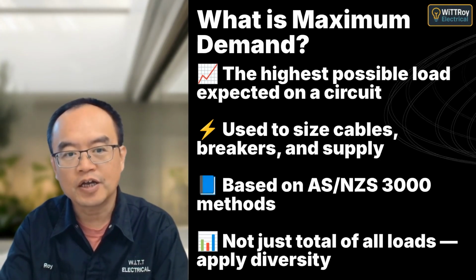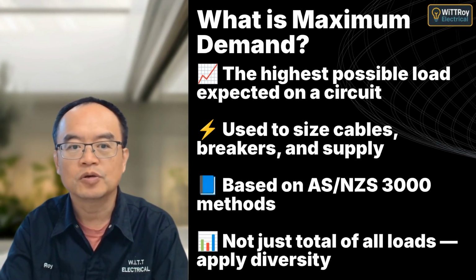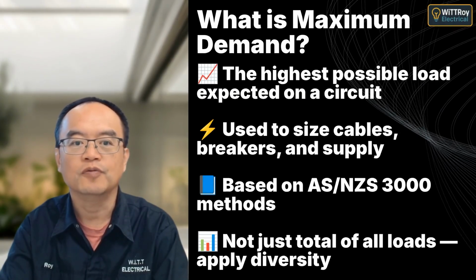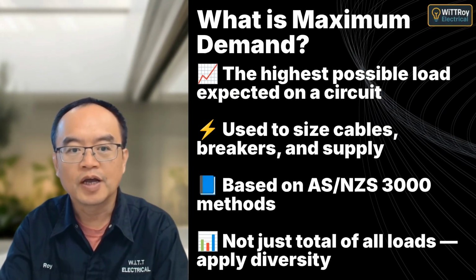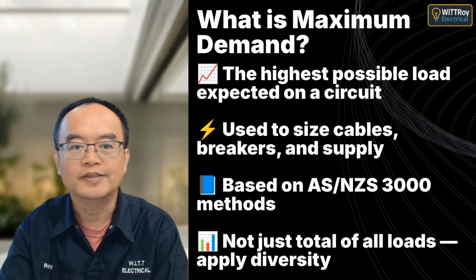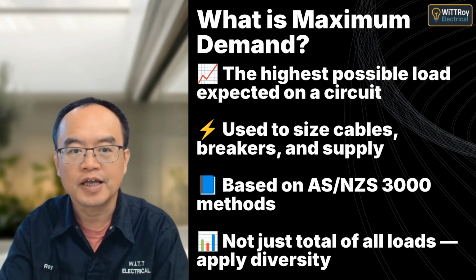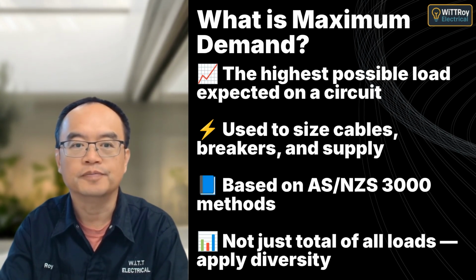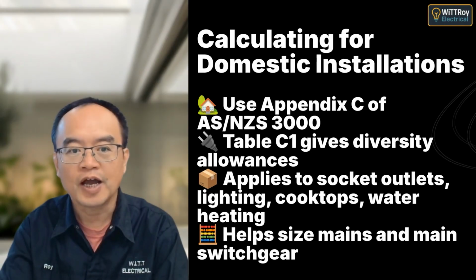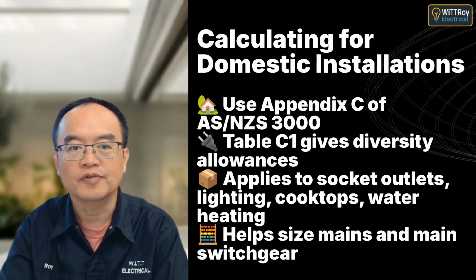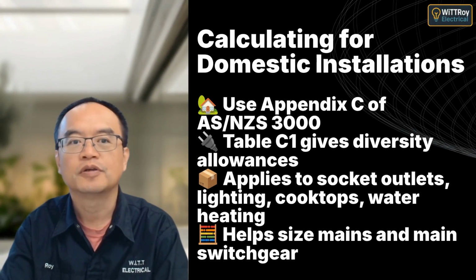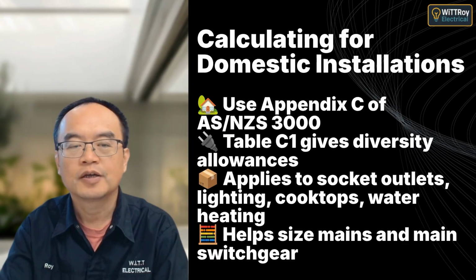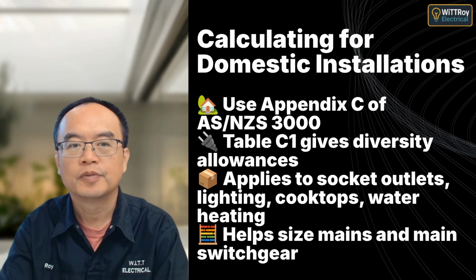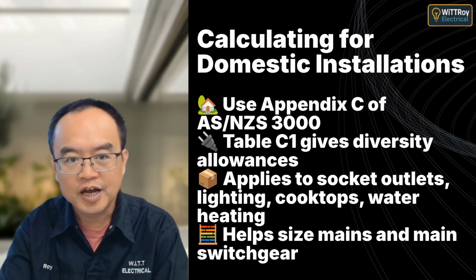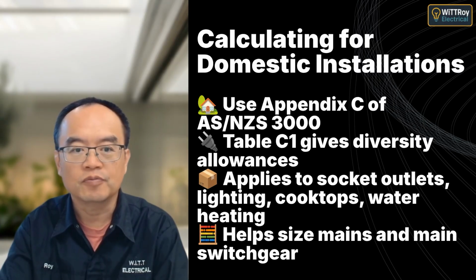Maximum demand is the calculated worst-case current a circuit may draw. It's not a straight sum of everything connected. We apply diversity factors from AS/NZS 3000 to reflect how loads behave in real life. For houses, use Appendix C Table C1 to find demand values for each load type. For example, multiple socket outlets are calculated with decreasing amperes by points. This ensures cables and fuses are right-sized for realistic use.